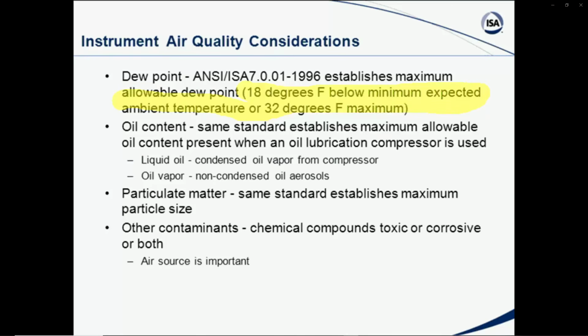So if you're working in the Upper Peninsula of Michigan outside, that's one situation. And if you're working in, say, Baton Rouge or Mobile outside, that's another situation. But in any event, you would want to have a dew point that is below your minimum expected temperature.